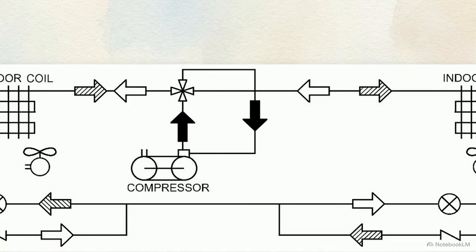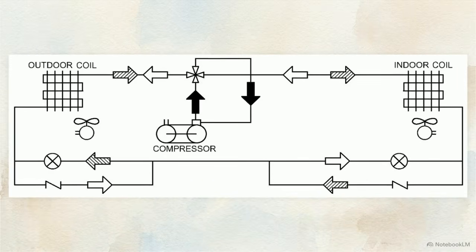Heating inside these advanced unitary and VRF systems is achieved by running the Rankine cycle in reverse, operating the equipment as an applied heat pump. In this technical schematic, focus on the four-way reversing valve assembly at the top center. This valve dictates the directional flow shift between the compressor and the coils, literally swapping the roles of the evaporator and the condenser in the refrigerant circuit.